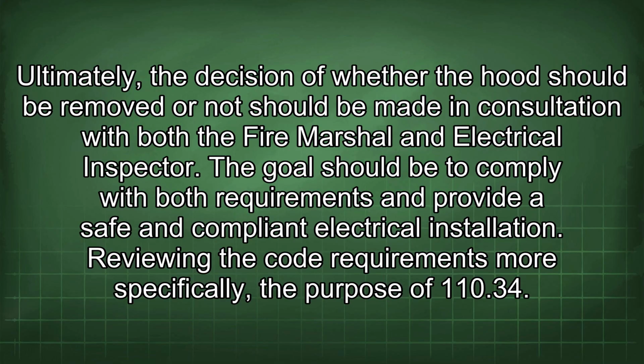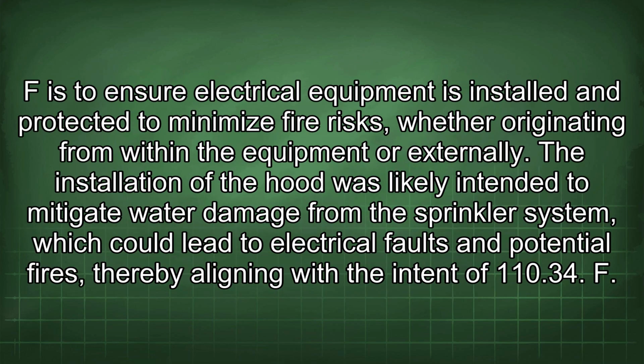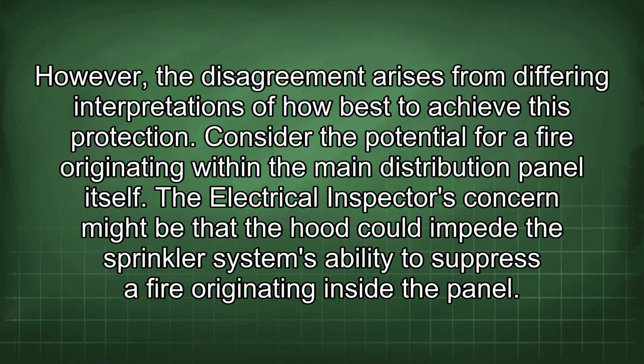Reviewing the code requirements more specifically, the purpose of 110.34.F is to ensure electrical equipment is installed and protected to minimize fire risks, whether originating from within the equipment or externally. The installation of the hood was likely intended to mitigate water damage from the sprinkler system, which could lead to electrical faults and potential fires, thereby aligning with the intent of 110.34.F. However, the disagreement arises from differing interpretations of how best to achieve this protection.